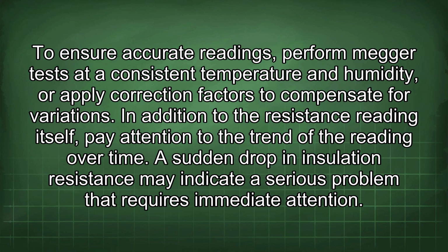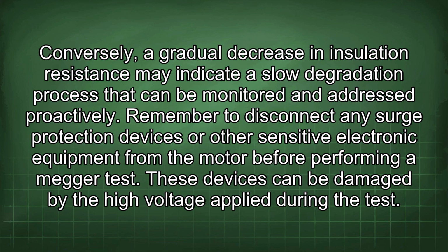A sudden drop in insulation resistance may indicate a serious problem that requires immediate attention. Conversely, a gradual decrease in insulation resistance may indicate a slow degradation process that can be monitored and addressed proactively. Remember to disconnect any surge protection devices or other sensitive electronic equipment from the motor before performing a Megger test. These devices can be damaged by the high voltage applied during the test.